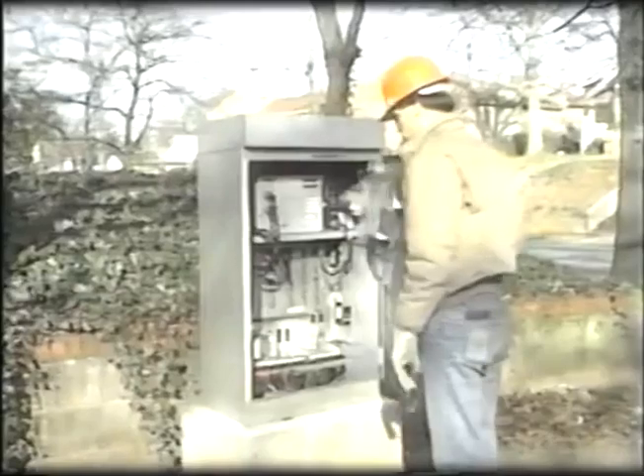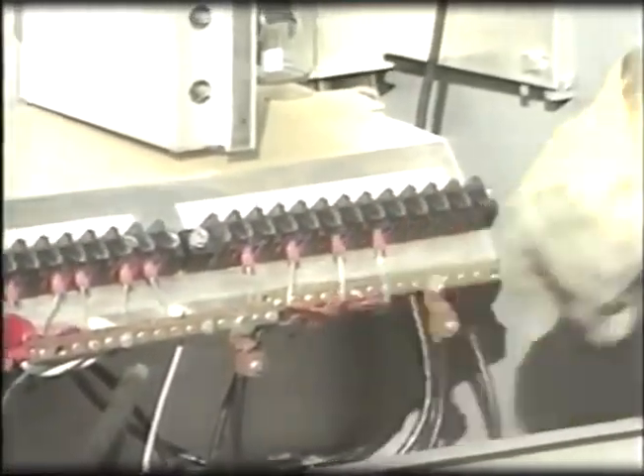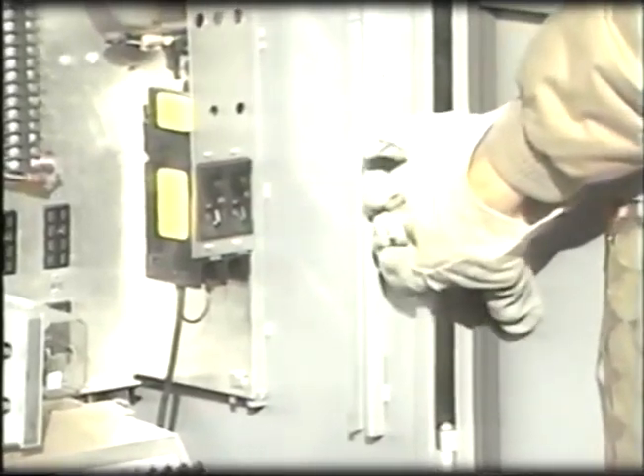These practices are not adequate for proper protector performance. Lightning grounds require a much lower impedance path to earth than safety grounds. They need to be short, wide metal paths to accommodate lightning pulses. That's why a metal cabinet is better than the wire specified by code.